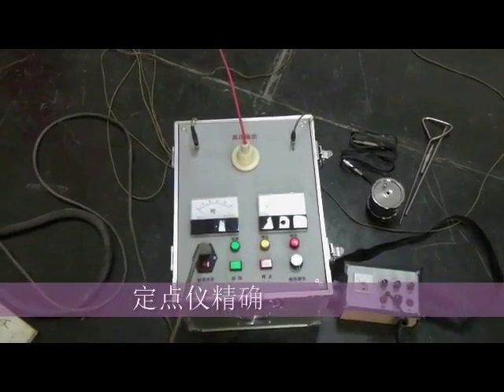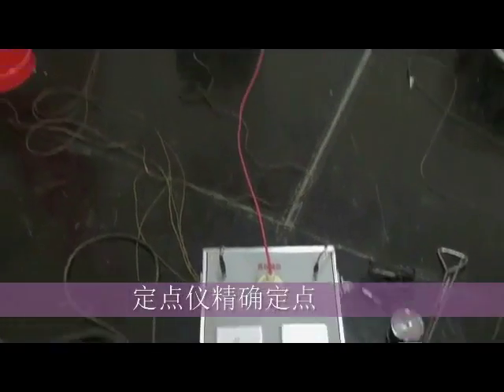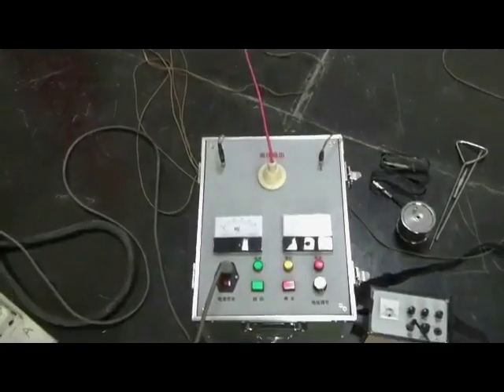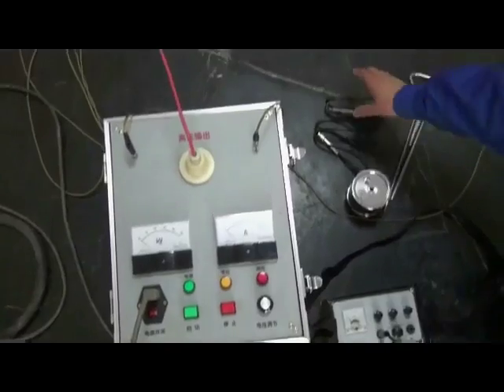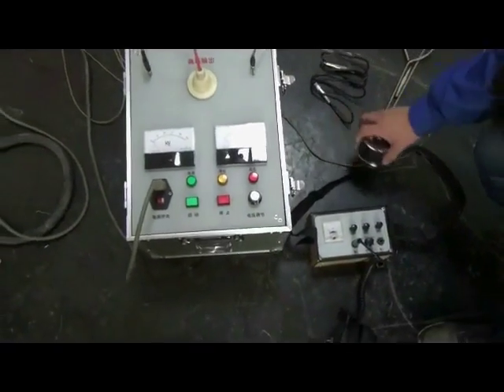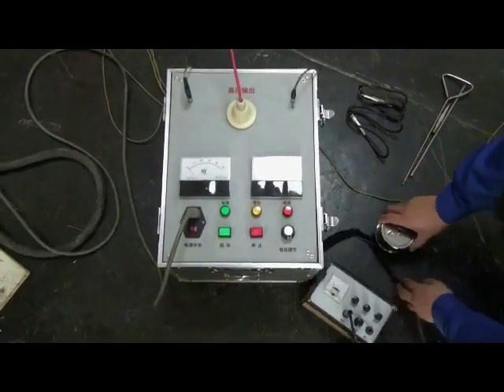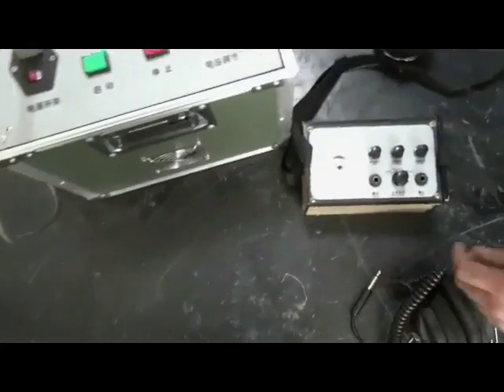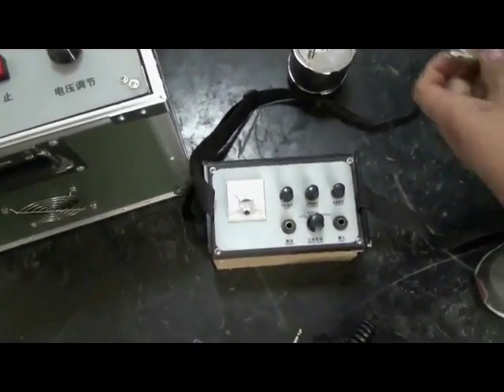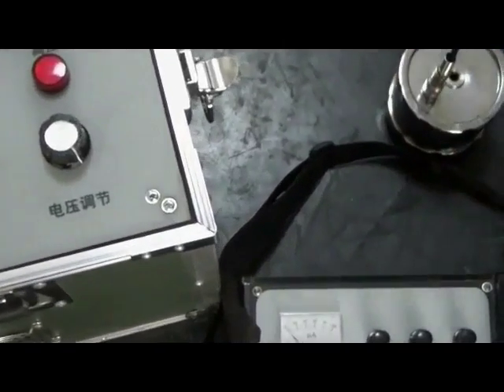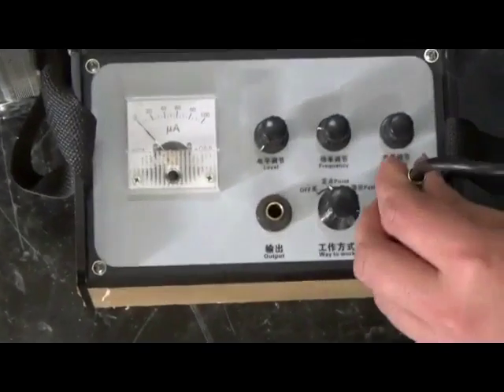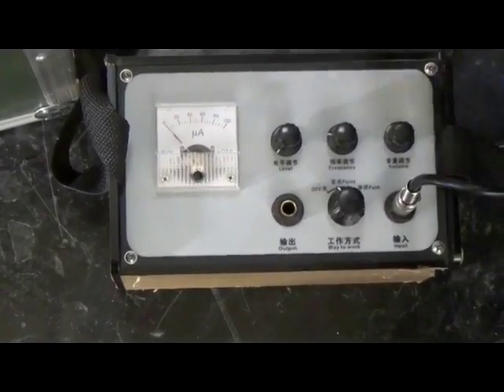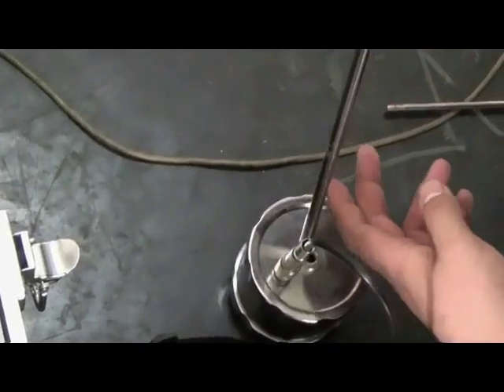Now we are starting to pinpoint cable fault. We need high voltage power supply and impulse capacitor to discharge for fault point. We also need pinpoint locator, probe, and audio line. One end of audio line is connected to probe, the other end connected to input terminal. Insert connecting rod to probe.